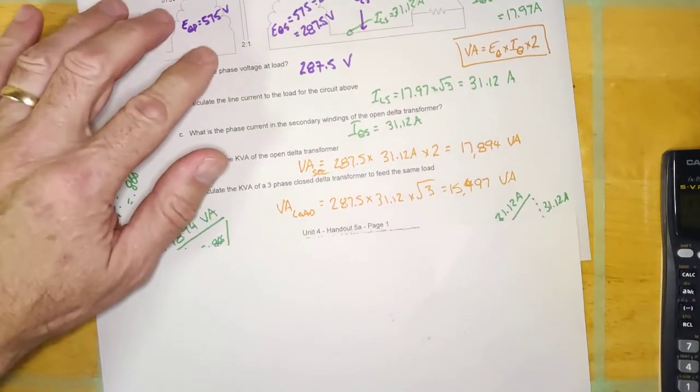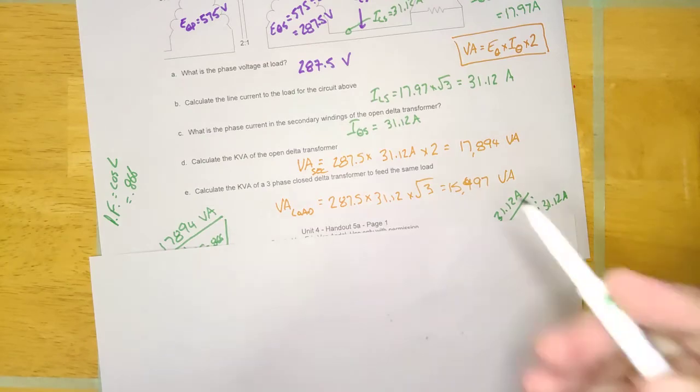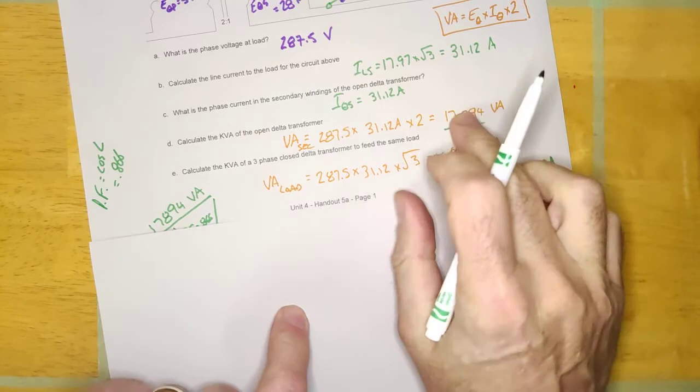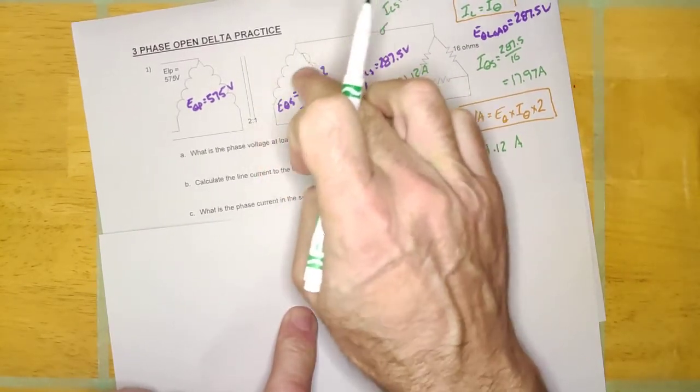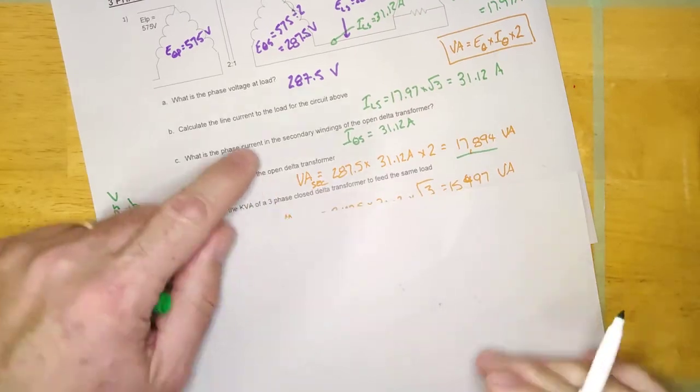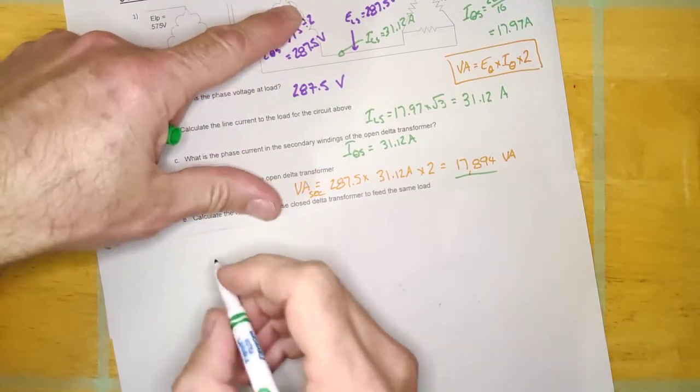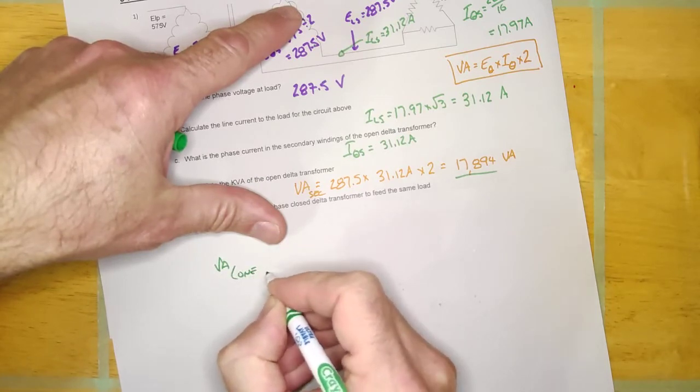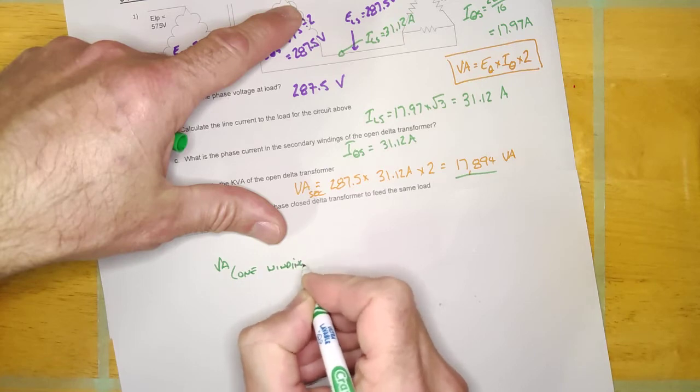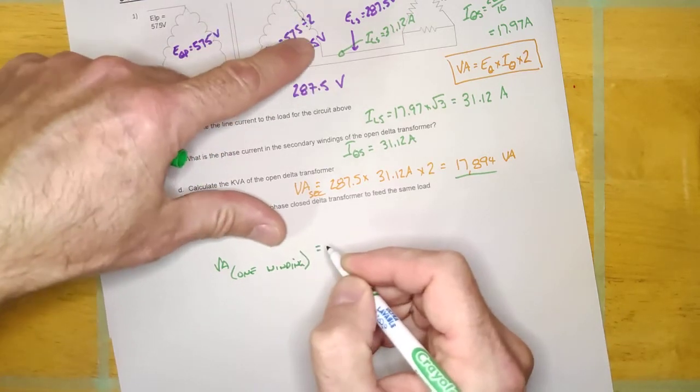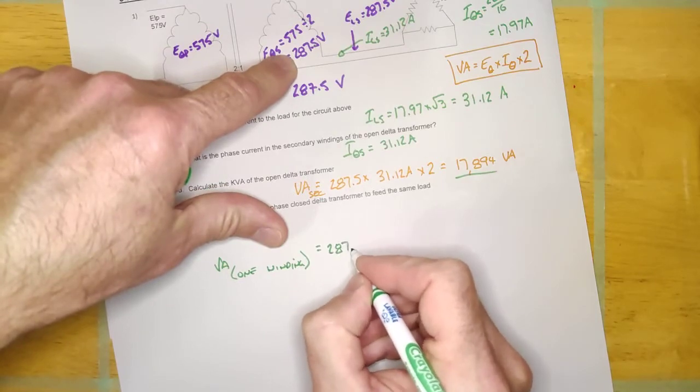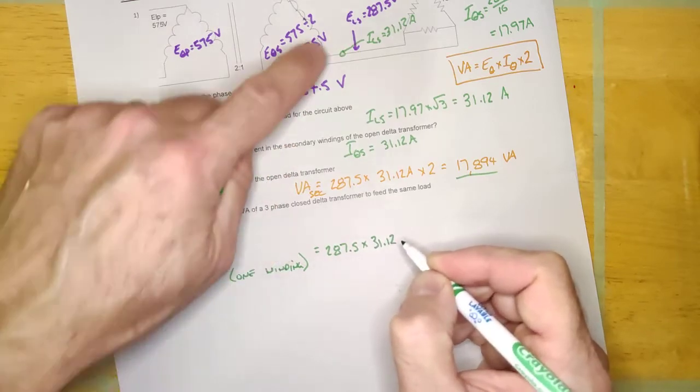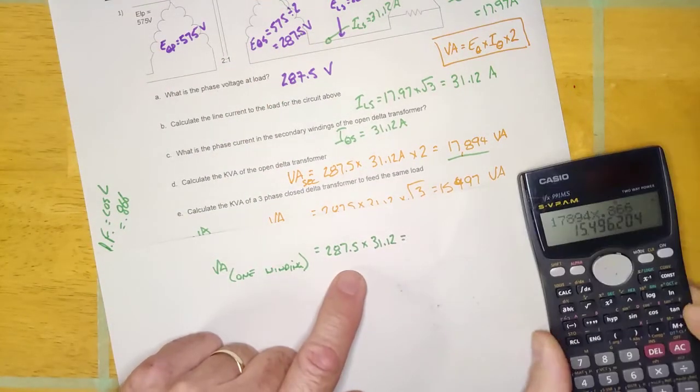Let's think about what's going on here. We've got an open delta transformer, we decided that it is 17,894 VA. If it's 17,894 VA, then each one of these will be half that, right? So basically the VA of one of these windings, let's calculate it. VA of one winding of the transformer is going to be this voltage, 287.5, times this current, 31.12. It's E phase times I phase.